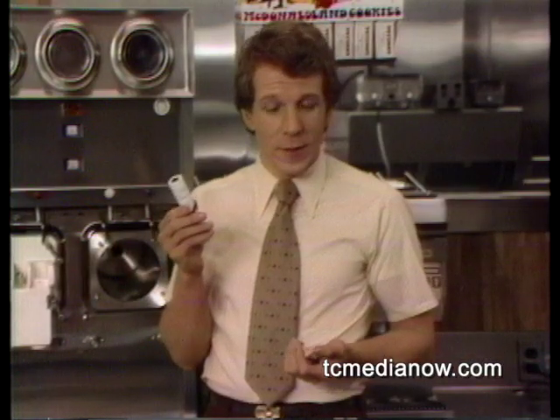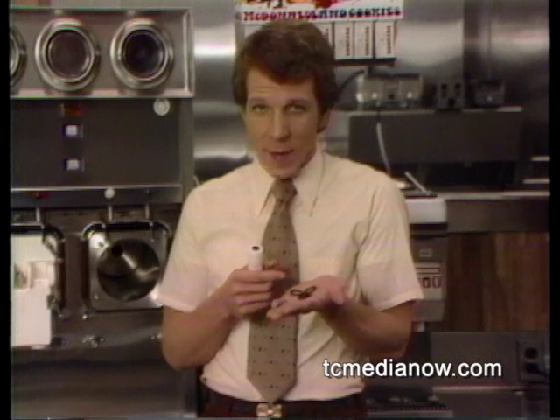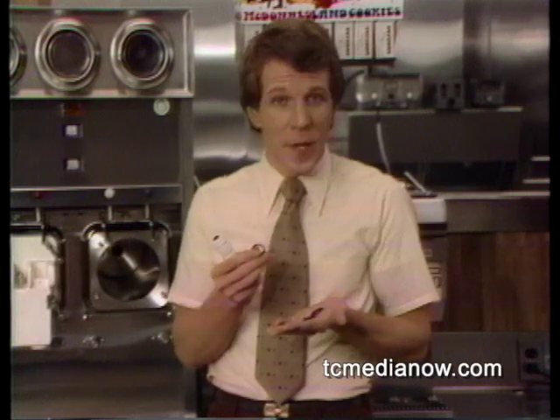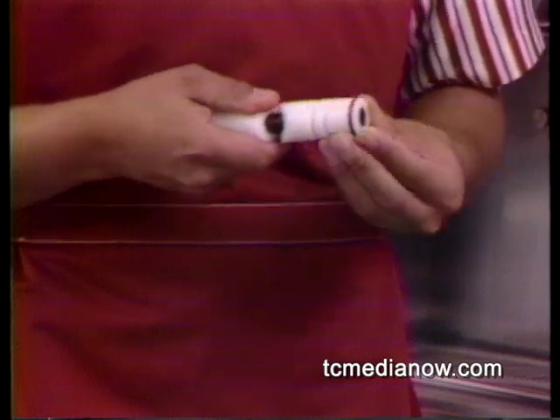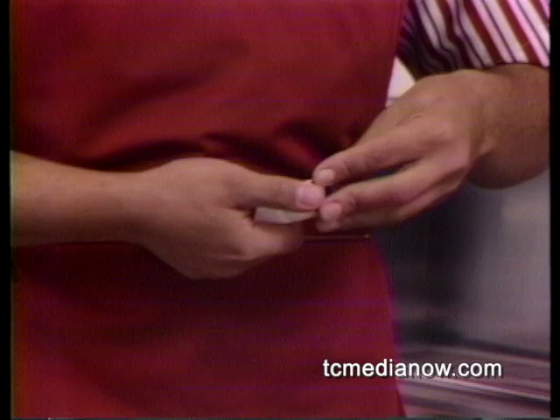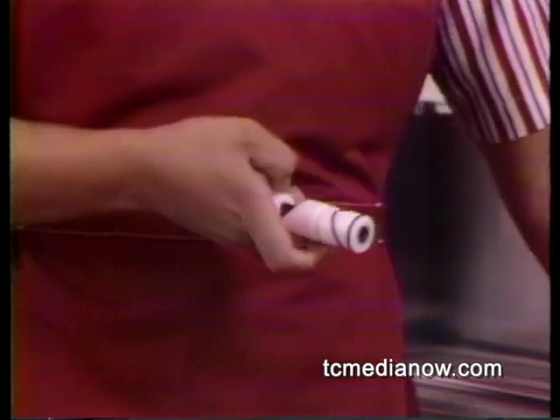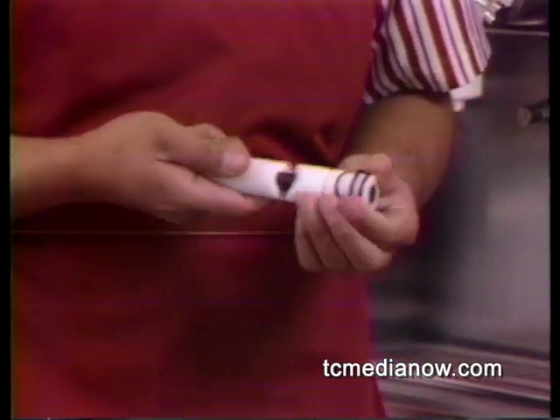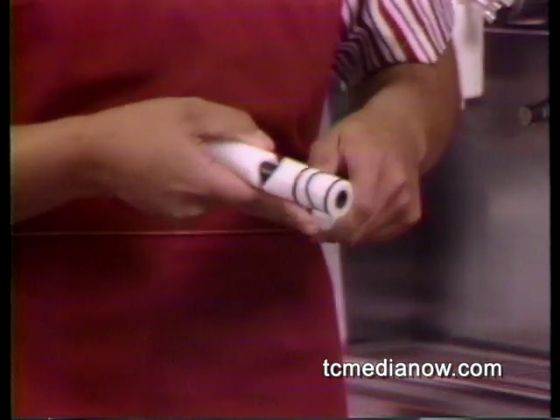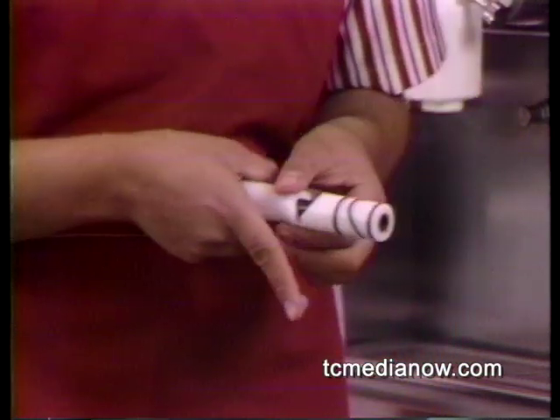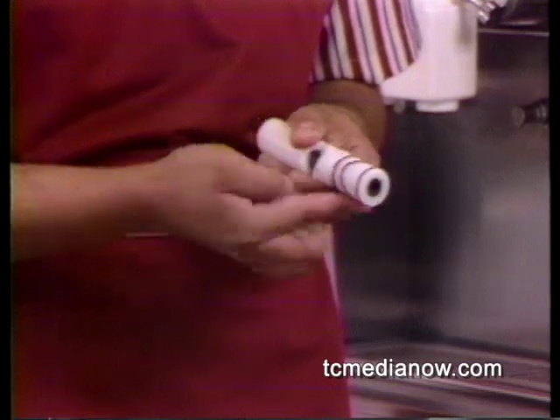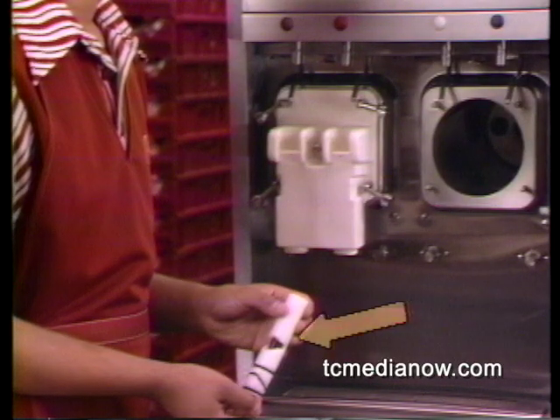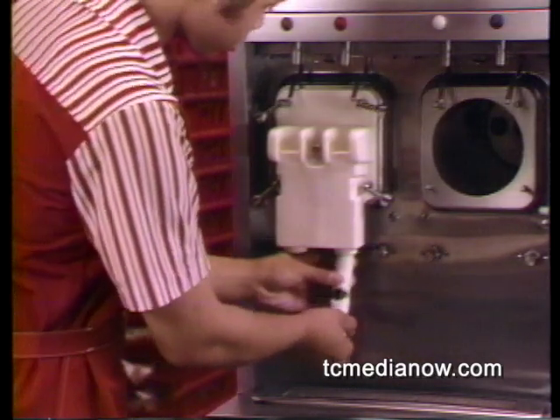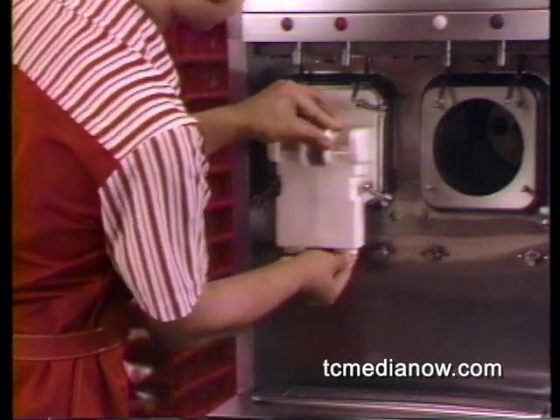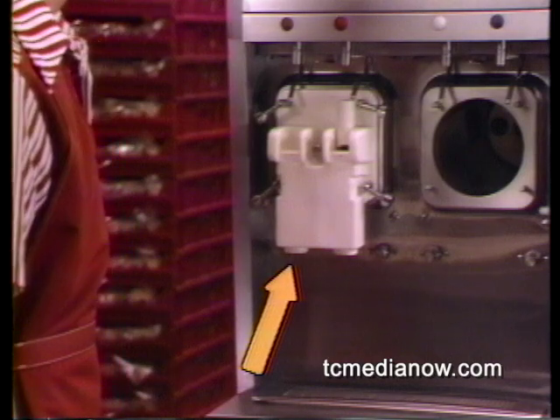This is the draw valve core. Inspect each of the 3 O-rings carefully for nicks and cuts. If any of them are damaged, they must be replaced. After inspecting the O-rings, put them on the draw valve core. Then lubricate the O-rings. Install the valve core into the door assembly with the handle slot toward you, and push it up from the bottom until you can see the handle slot at the top. Do the same thing with the other valve core for this chamber.